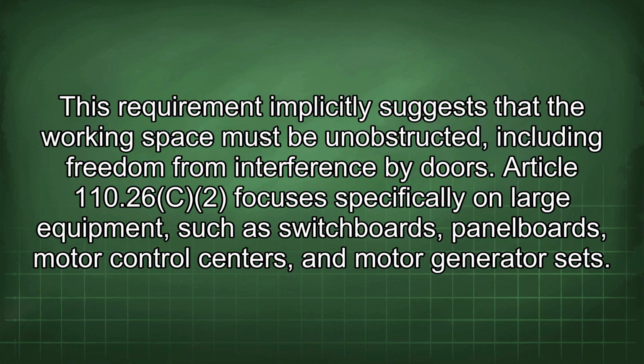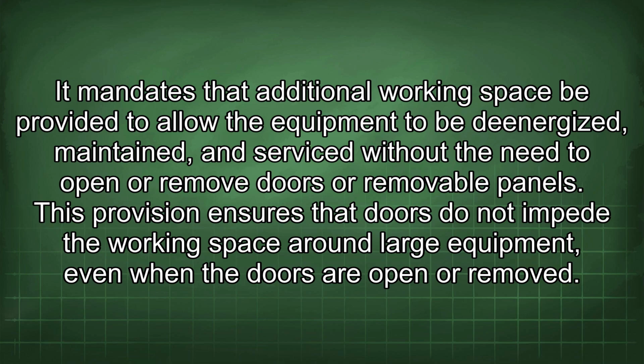Article 110.26(C)(2) focuses specifically on large equipment, such as switchboards, panelboards, motor control centers, and motor generator sets. It mandates that additional working space be provided to allow the equipment to be de-energized, maintained, and serviced without the need to open or remove doors or removable panels.